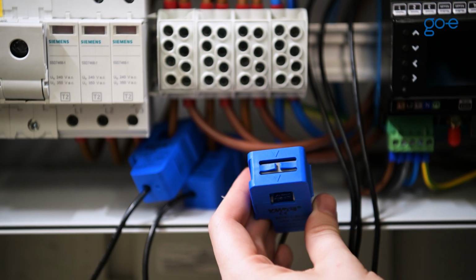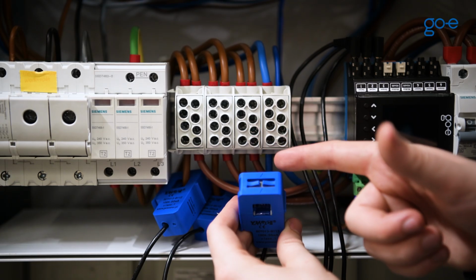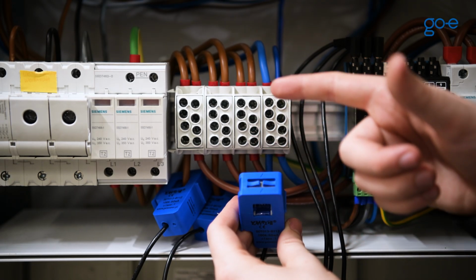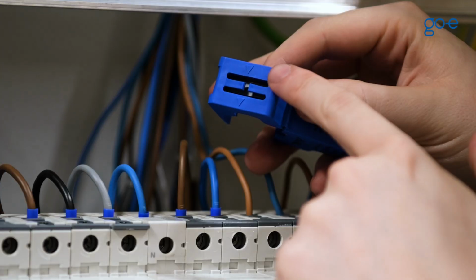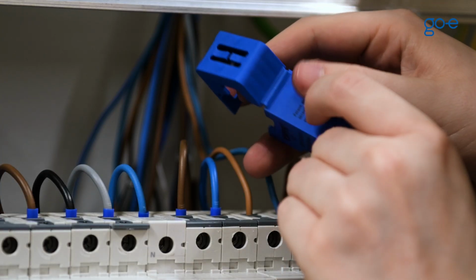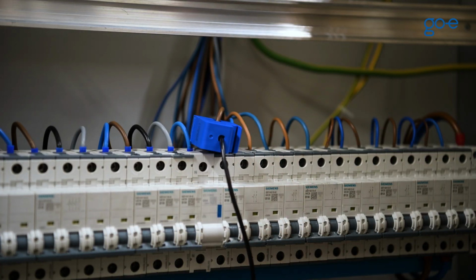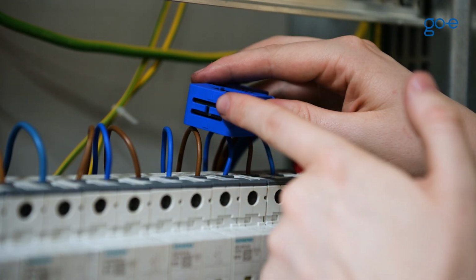The 2 arrows on each current transformer must point in the direction of current flow. When connecting to the grid, which we refer to as the mains, the arrows should point from the grid towards the house. For a solar inverter or AC battery, the arrow should point from the inverter or battery towards the distribution board. When measuring other loads, such as a boiler, the arrow should point towards the load.